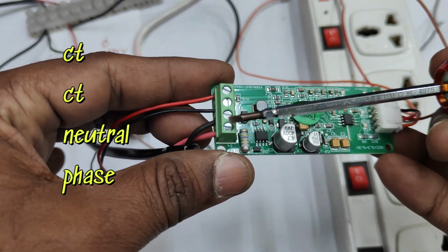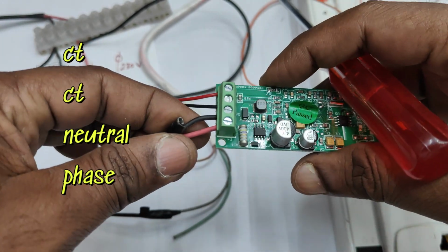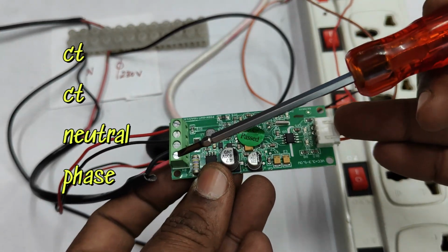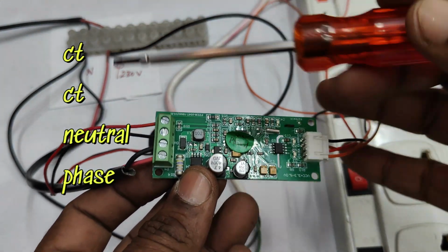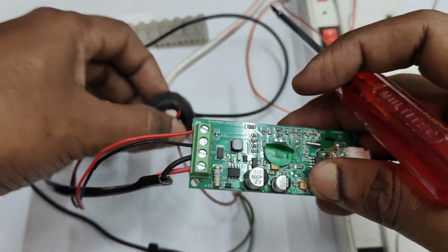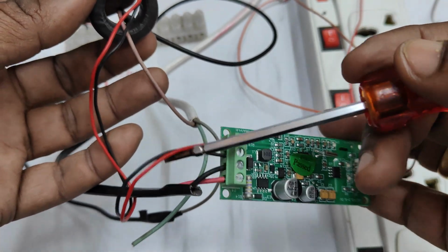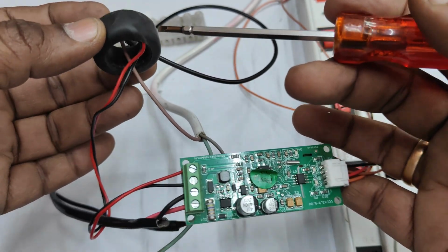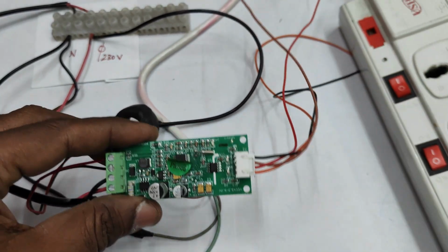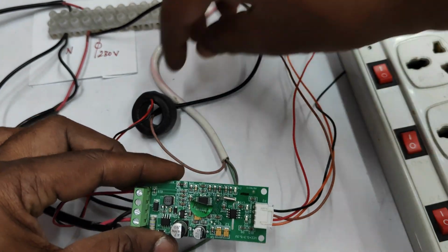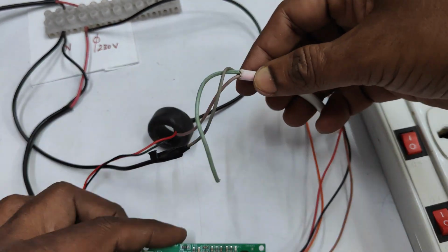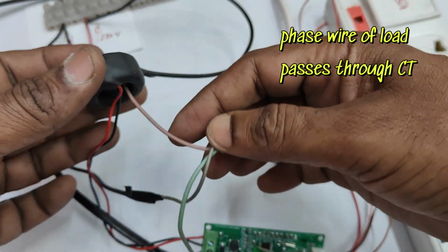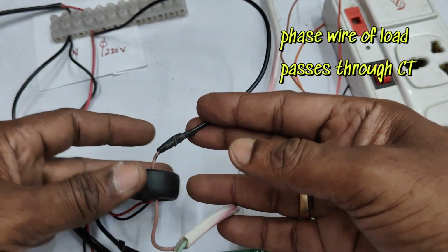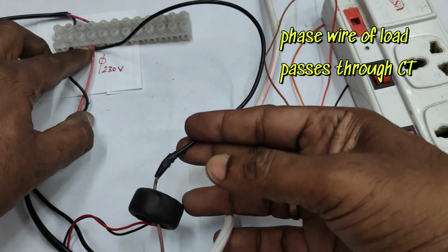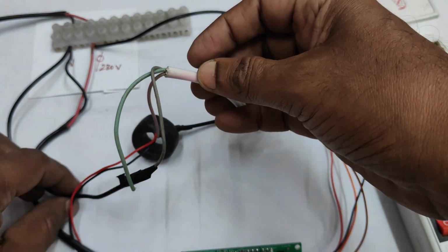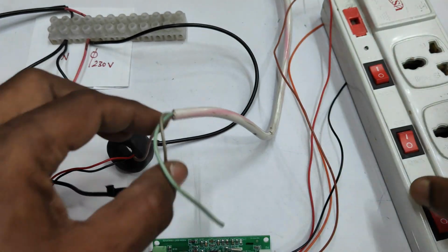Let us see the connection. At the left hand side, screw terminal, at the top two terminals you have to connect the current transformer. At the bottom two terminals you have to connect the neutral and phase of the input, that is the 230 volt AC. And through the current transformer you have to pass the phase wire of the load. So the phase wire of the load should pass through this current transformer and reach the phase. The other end of the load, that is the neutral wire, goes directly to the neutral. This pass-through connection is very important to sense the energy values.